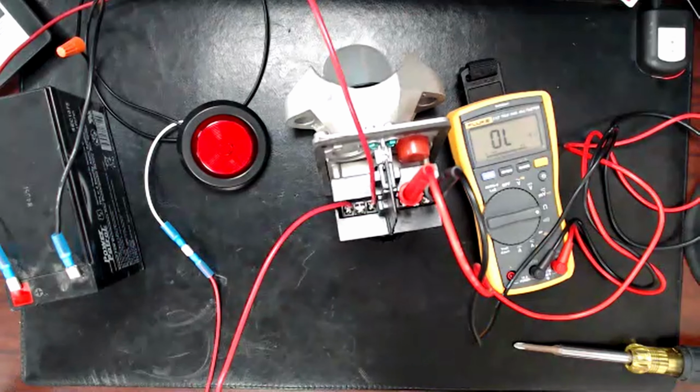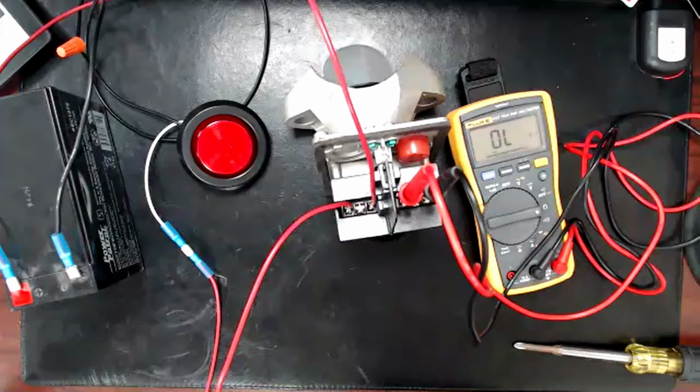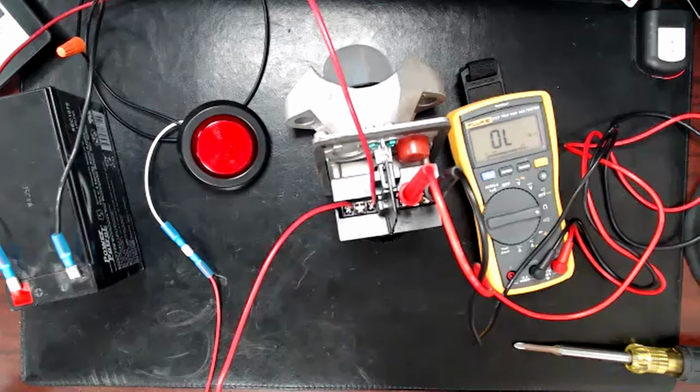But if you're putting in, say, an IFP 75 or a Gamewell 7075, those are the same panel. I think that's the next series I'm going to do. We've done switches for several weeks. I think we're going to come back and I'm going to start getting into the different panels, and we'll do detailed videos on each panel. But if you're putting in one of those, you've only got 2 NAC circuits on it. One of them has to go to the NAC devices that are there.